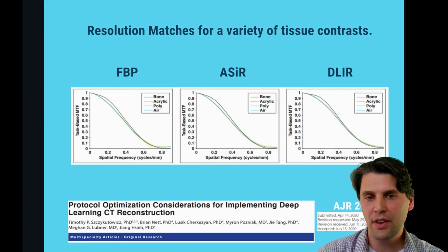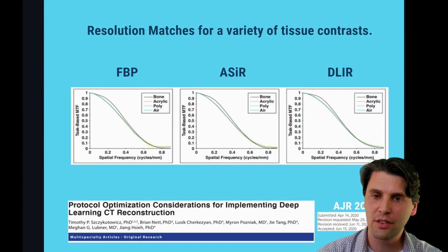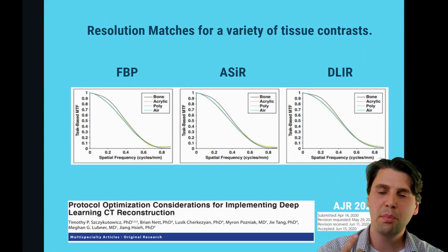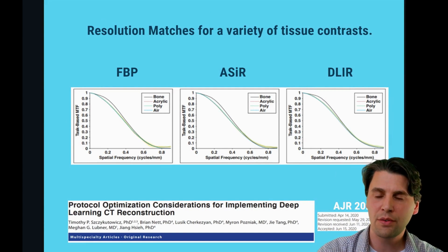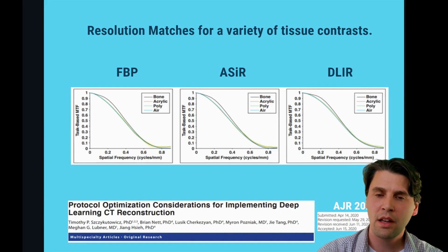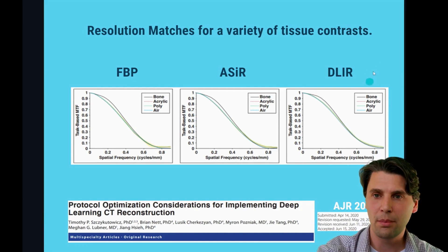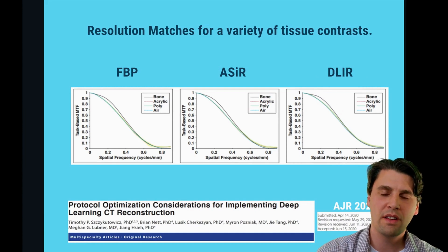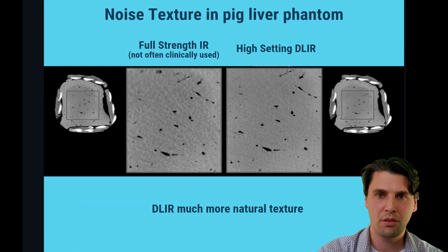The MTF can be measured for different tasks or different tissue types. This is the work of Szczykutowicz et al., and this demonstrates that for each of these technologies — FBP, ASIR, and DLIR — in comparison with previous techniques for iterative reconstruction, all of these technologies demonstrate good agreement of the MTF as a function of different tissue types. The MTF for deep learning well matches the filtered back projection results.